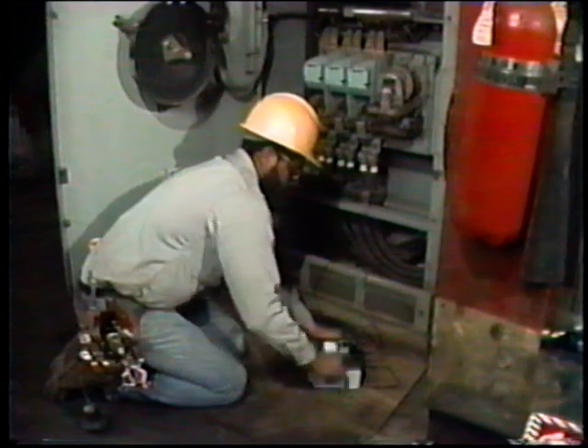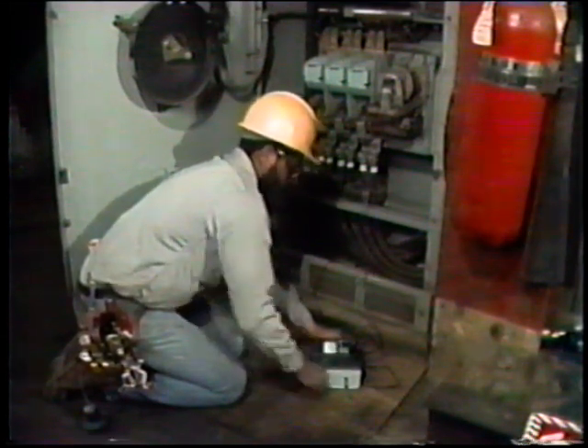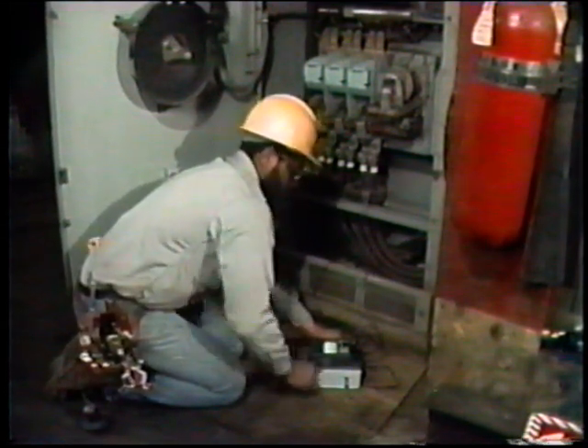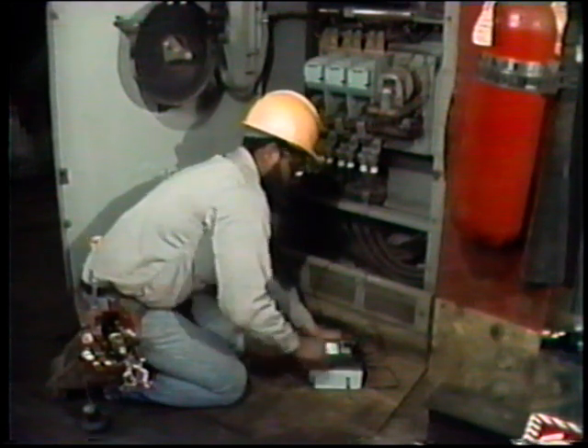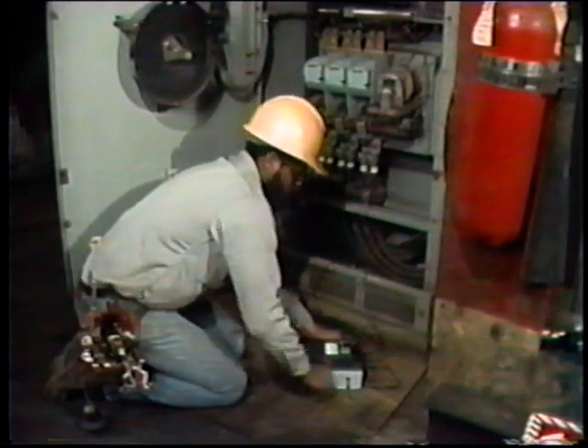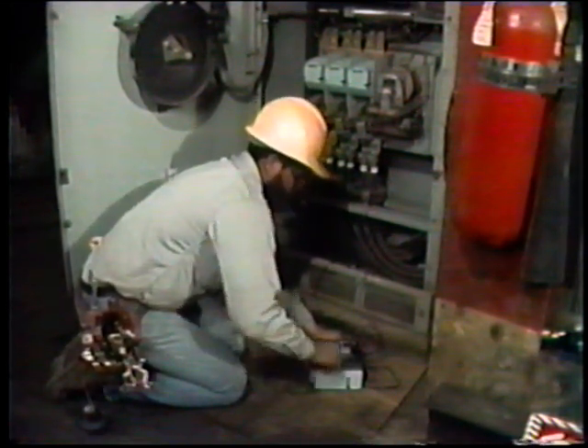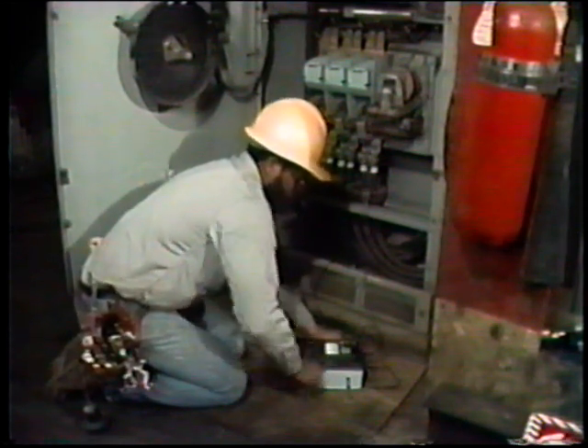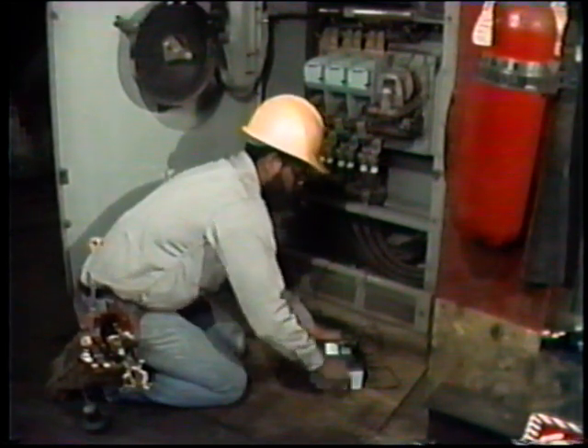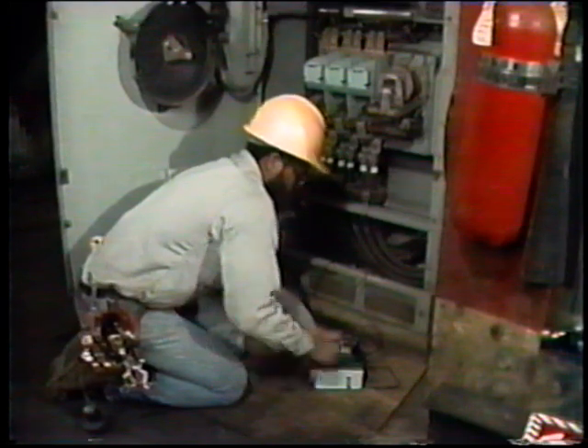A meg-ohm meter is used to test the resistance of the circuit's insulation. Remember, as a rule of thumb, a reading of at least 1 meg-ohm for each 1,000 rated volts with a minimum of 1 meg-ohm should be indicated on the meter. If it isn't, a ground may exist in the component. Now, to test a controller for both opens and shorts, a multimeter will usually be used, and a resistance reading is taken across the component in question.